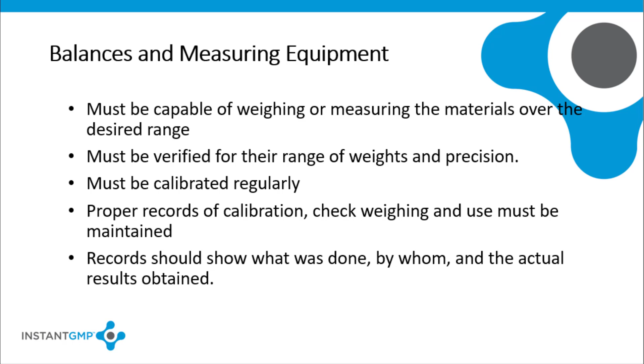Although calibration is done at regular intervals, check weighing should be done on a daily basis. Records should show that the check was done, by whom, and the actual results obtained. An example of a record in an equipment log for a floor scale is shown. This shows that the floor scale was used for production of a batch of material, when it was done, and how the scale was cleaned.